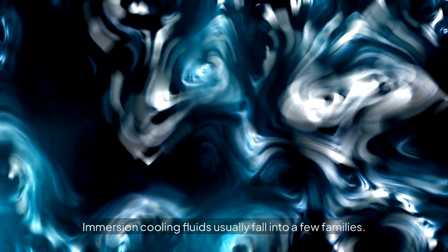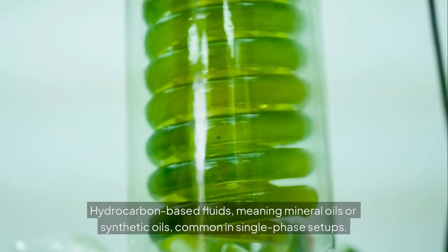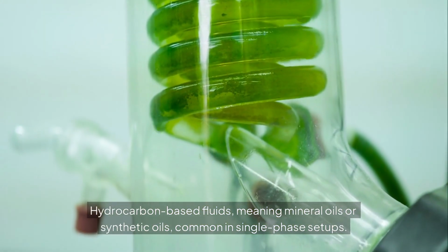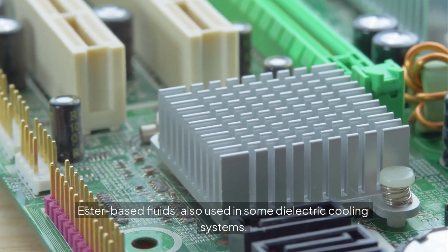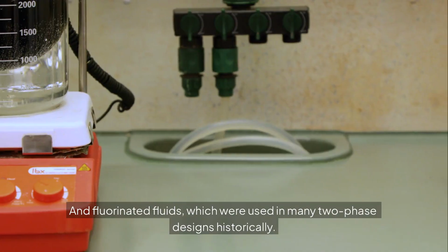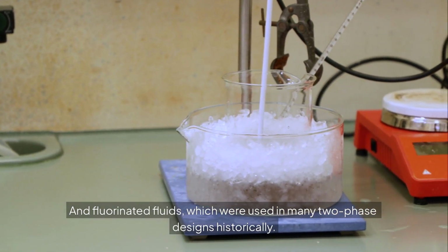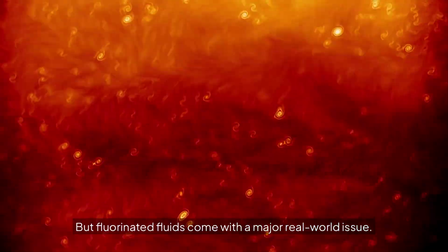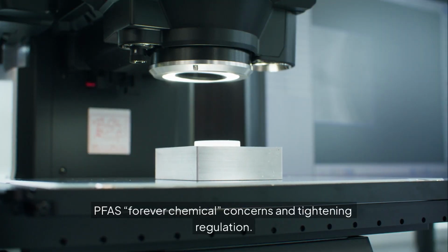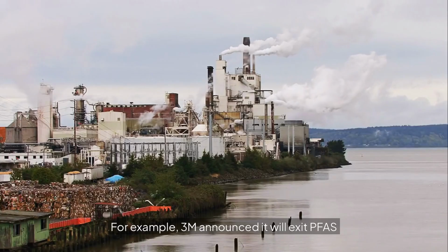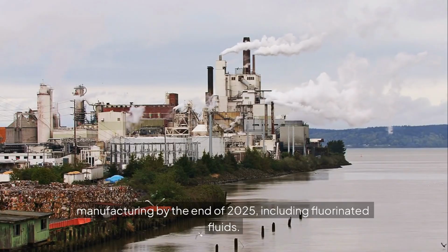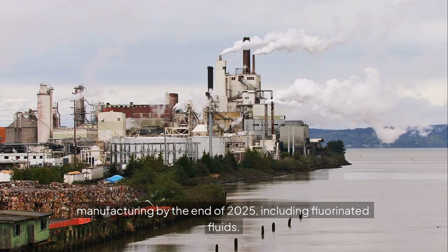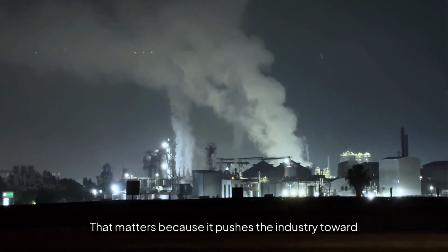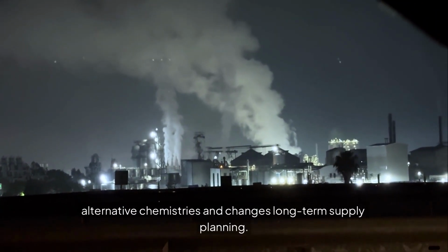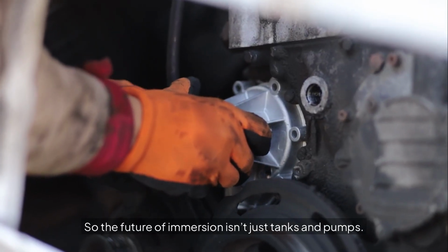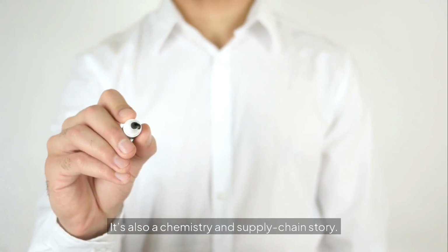Immersion cooling fluids usually fall into a few families. Hydrocarbon-based fluids, meaning mineral oils or synthetic oils, common in single-phase setups. Ester-based fluids, also used in some dielectric cooling systems. And fluorinated fluids, which were used in many two-phase designs historically. But fluorinated fluids come with a major real-world issue. PFAS, forever chemical concerns, and tightening regulation. For example, 3M announced it will exit PFAS manufacturing by the end of 2025, including fluorinated fluids. That matters because it pushes the industry toward alternative chemistries and changes long-term supply planning. So the future of immersion isn't just tanks and pumps. It's also a chemistry and supply chain story.